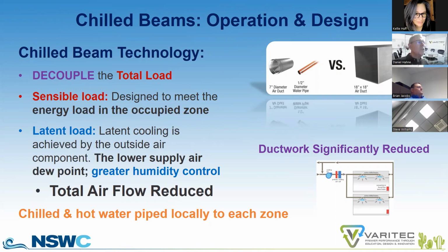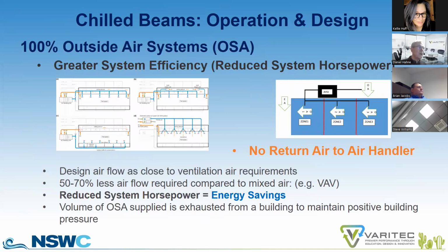If you shift the sensible load to the chill water loop, you can significantly reduce your total airflow to a building. I'll never forget working with Henry Johnston of GLHN when he was laying out the University of Arizona Environmental Natural Resource Building. One of the first things he said when he laid out the hybrid active and passive system was, my gosh, Dad, what happened to all my duct work? He was designing rooms, depending on their application, down to 0.25 CFM per square foot. We normally see about 0.3 to 0.4, and you do more if you're serving a laboratory, but your duct work is significantly reduced. By the way, GLHN won an ASHRAE award for energy performance nationally a couple of years ago. I was really excited to hear the news from Henry before he retired from GLHN.